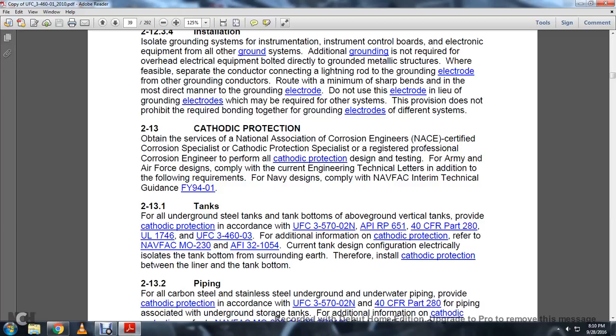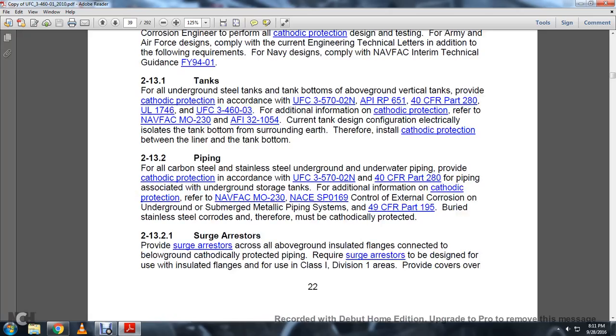213.1 Tanks. Underground steel tanks and tank bottoms of the aboveground vertical tanks are to be provided with cathodic protection in accordance with UFC 3-570-02N, API RP 651, 40 CFR Part 280, UL 1746, UFC 3-460-03. For additional information on cathodic protection, refer to NAVFAC MO 230 and AFI 32-1054 for current tank designs and configuration. Electrical isolation of the tank bottom from the surrounding earth is required. Therefore, install the cathodic protection between the liner and the tank bottom.